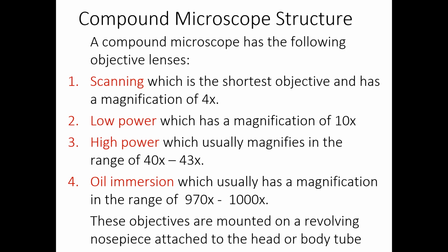And if that's still not what you need, you can turn the nosepiece one more notch, and you'll bring up the high power objective lens, which has a 40 stamped on it in blue. 40 times the ocular power gives you 400 magnifications. However, you'll also notice that your field of view has shrunk considerably, and the image has gotten dimmer because there's less light coming in.